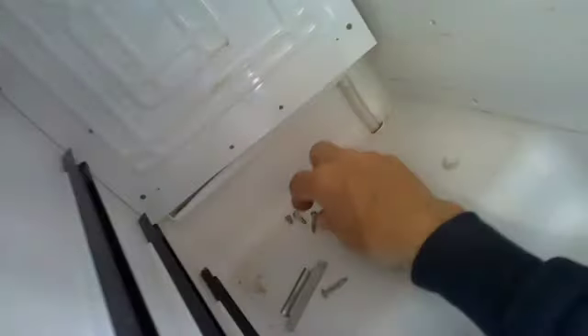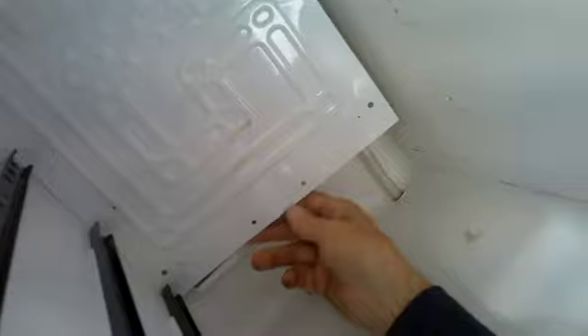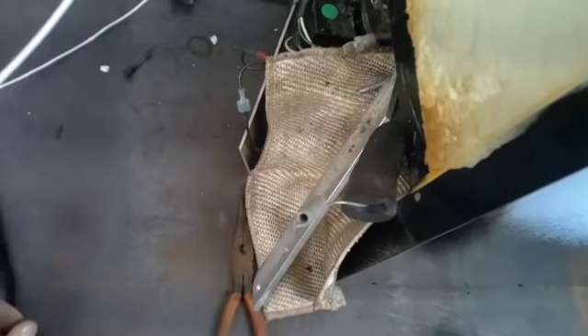There's the insulation that came with it to wrap that suction line up. All right, so now we've pretty much got it positioned, so I'm going to drill some holes into the plastic wall in the back and mount these screws with these little spacers on them. Hook in the feeler bulb for the thermostat, and then we'll connect the suction line to the compressor and put a new filter dryer on here and pull a vacuum on it, and we'll see how things work. Stand by. Okay, so we have the screws on top holding the plate in.